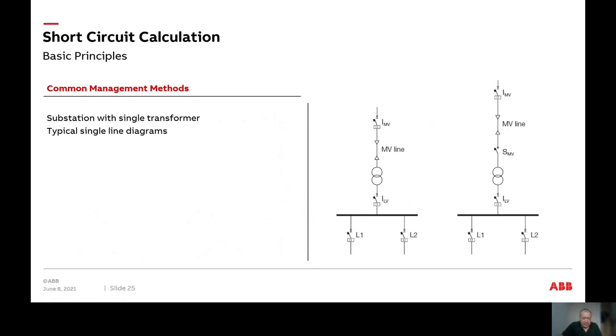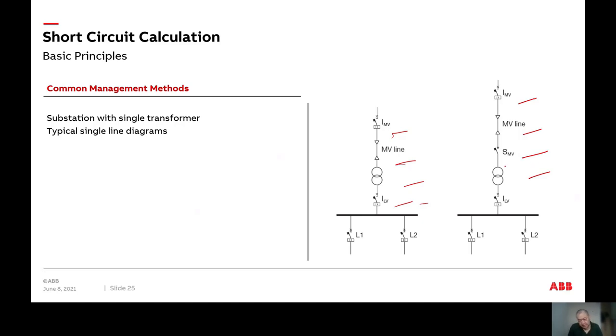On the right you can see two single line diagrams — both are basically the same, just different representations. The first has no switch disconnector, only a circuit breaker followed by cable, transformer, and LV cable. The second has a medium voltage circuit breaker, cable, an isolator or switch disconnector, then the transformer — it's practically the same with just an additional isolating function before the transformer.